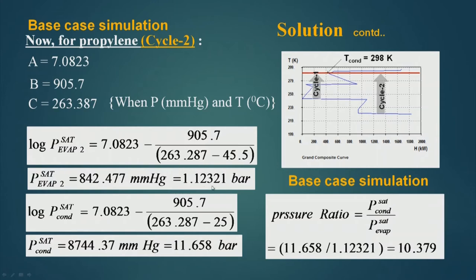For cycle 2, the evaporator pressure is 1.12321 bar and the condenser pressure remains the same at 11.658 bar. So the pressure ratio is 11.658 divided by 1.12321, which comes out to be 10.379. This compression ratio is very high, and generally for such a ratio a single compression is not used because energy consumption will be more. However, for the present case a single compression will be used for comparison purposes.